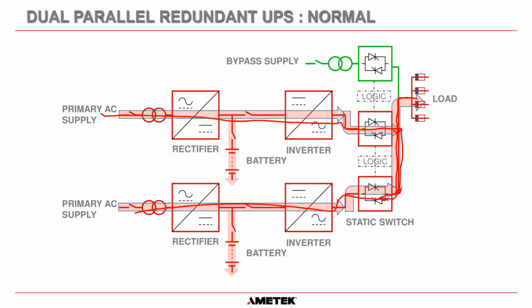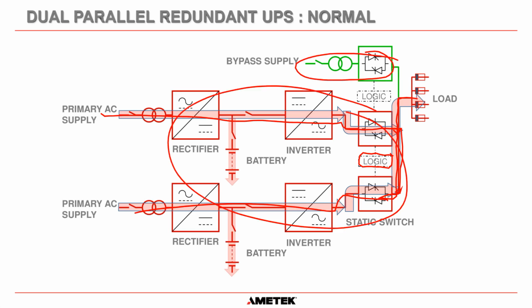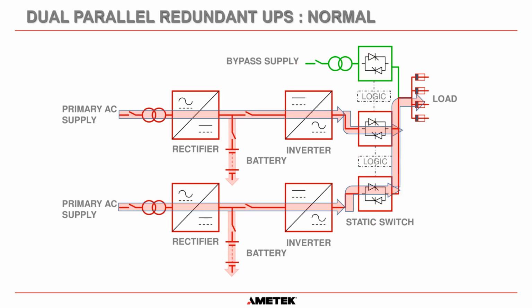And then there is internal logic inside the UPS that monitors each UPS, and it will change as load increases or decreases, as power factor increases and decreases with different loads. Then the logic will make sure that both UPSs share the load at all times. Okay, but we still have the bypass supply available just in case both UPSs fail. We still want to have a backup supply. So that bypass is sitting there just in case both UPSs fail, or you're going to do maintenance on both UPSs for some reason. Okay.